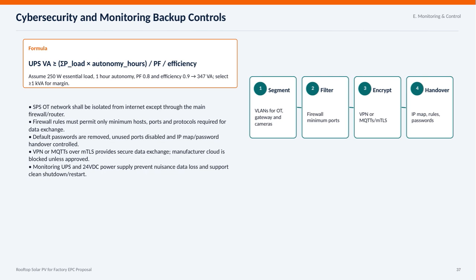On the cybersecurity side, several key controls ensure secure and reliable operation. First, the SPS OT network should be isolated from the internet except through the main firewall or router. Firewall rules are restrictive, permitting only the minimum necessary hosts, ports, and protocols for data exchange. Default passwords are removed, unused ports disabled, and IP mapping and password handovers are tightly controlled. Secure communication is maintained via VPN or MQTTs using mutual TLS authentication. Access to the manufacturer's cloud is blocked unless explicitly approved. Lastly, monitoring the UPS and 24V DC power supplies prevents unnecessary data loss and supports clean system shutdown and restart.